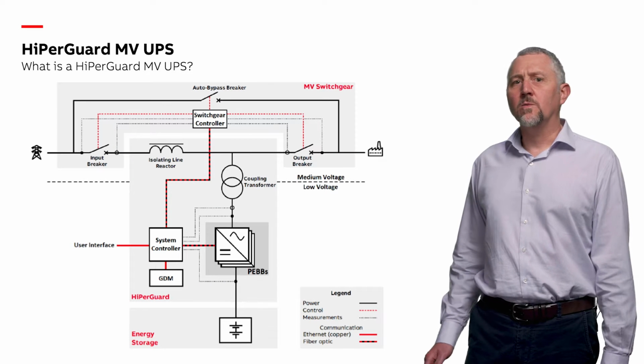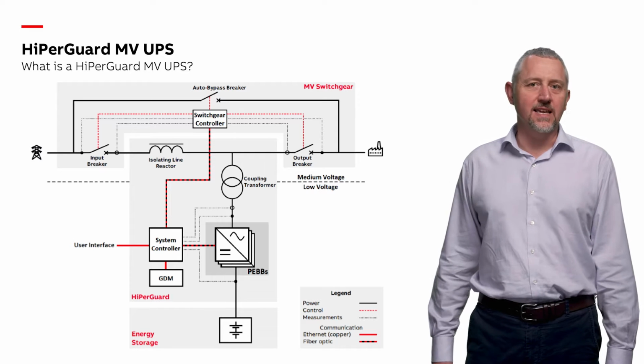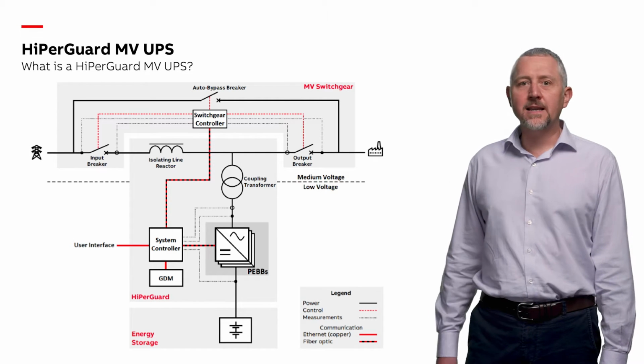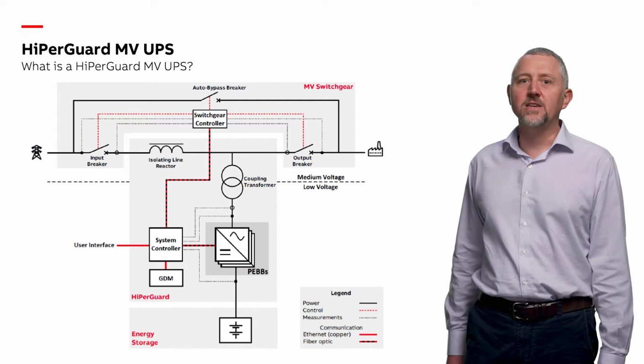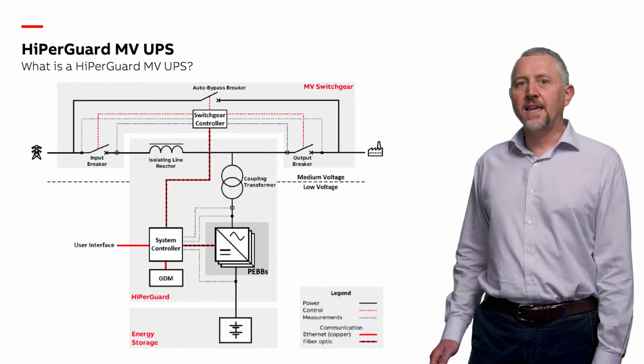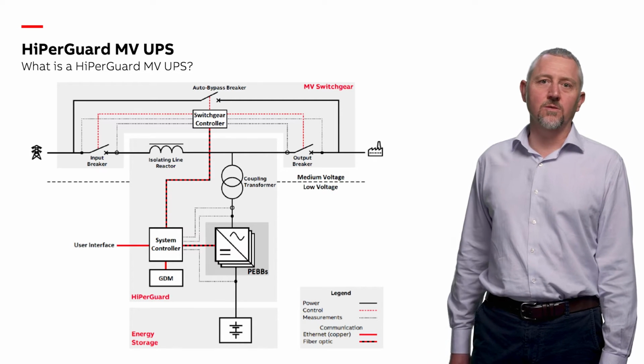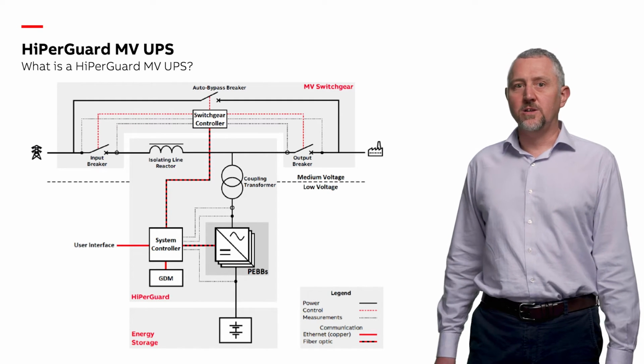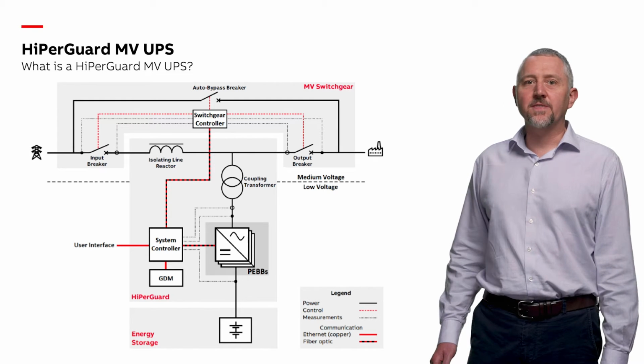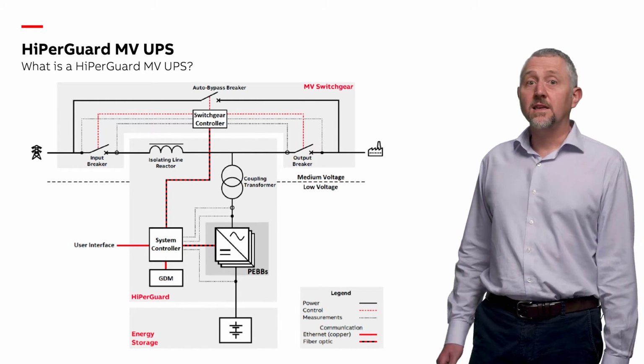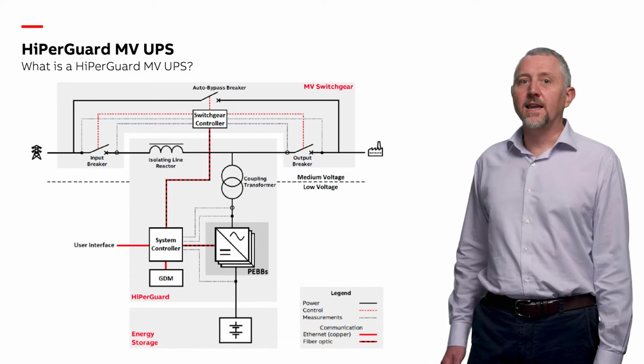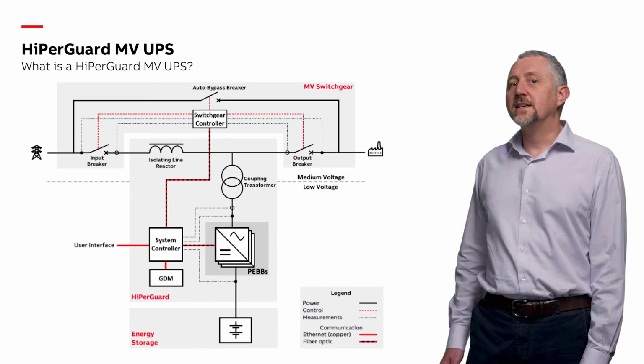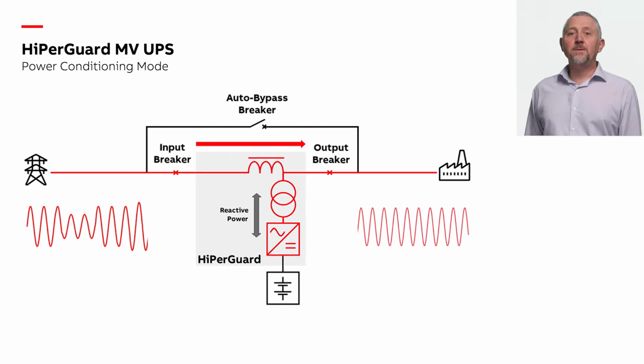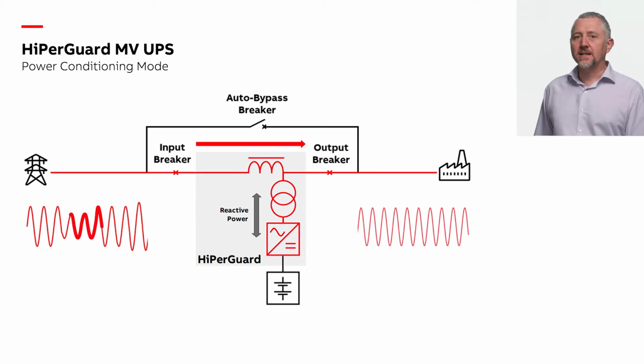You may now wonder what a HiPerGuard MV UPS actually is. In this slide, we can see the main components that make up the HiPerGuard MV UPS. At the top, we have the external MV switchgear and control. In the MV section of the UPS, we have the isolating line reactor and the coupling transformer. Conversely, the power electronics and the system control lie in the LV section of the UPS, which in turn is connected to the energy storage. The main purpose of the HiPerGuard is to supply perfectly balanced three-phase voltage to the load, whilst assuring that the load's active power requirements are provided by the utility.